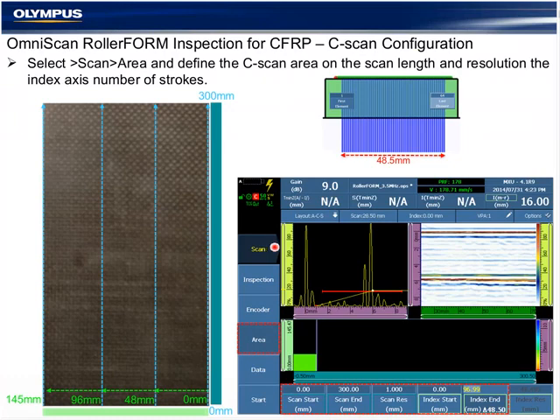Select Scan, Area, and this is where we define the C-scan. Since we selected a raster scan under the inspection type, we have available parameters for the scan axes, which would be axis 1, which is slave to encoder 1, and an index axis that is applicable to the green ruler, which is a function of the width of the probe. So initially, when I click this, the software is automatically determining the beam-to-beam center point from my current configuration.